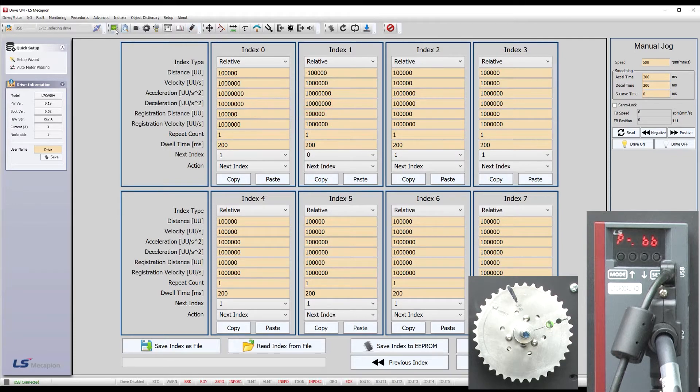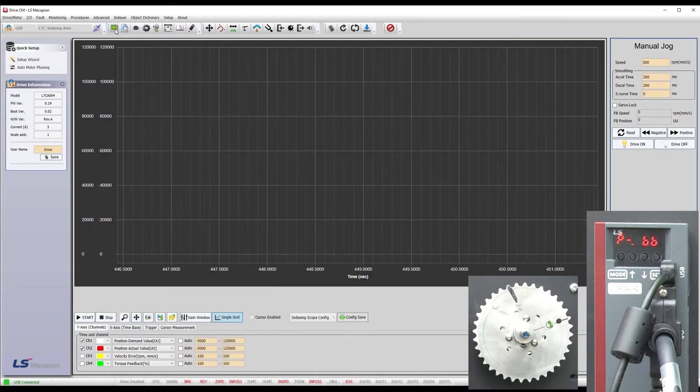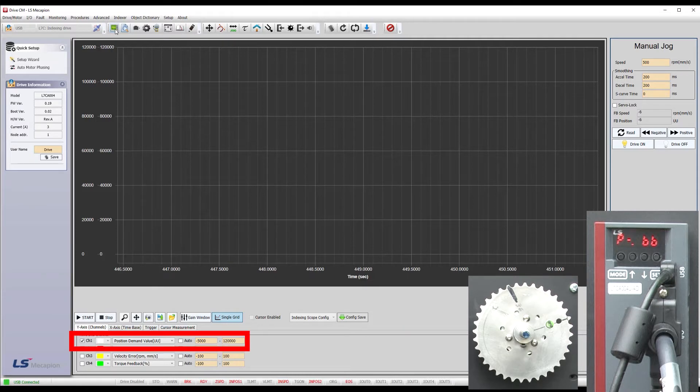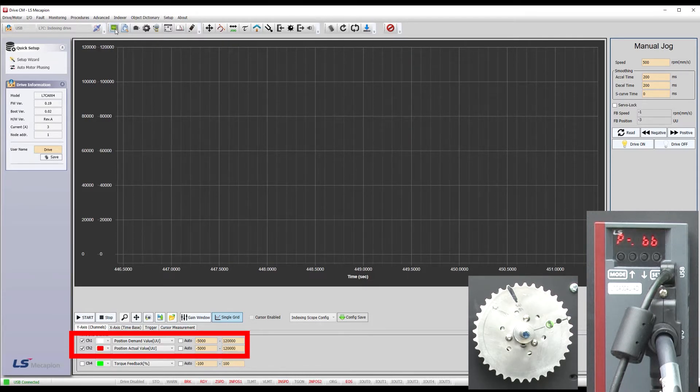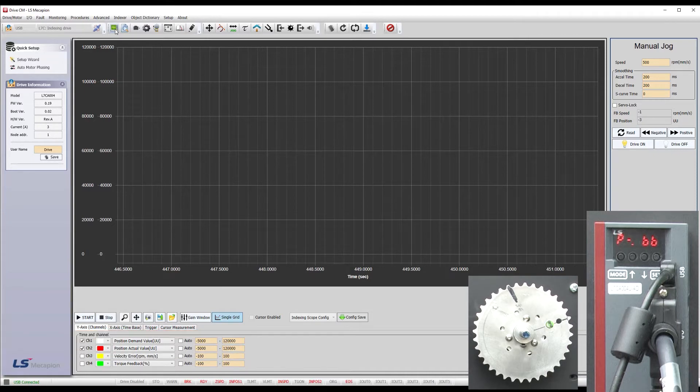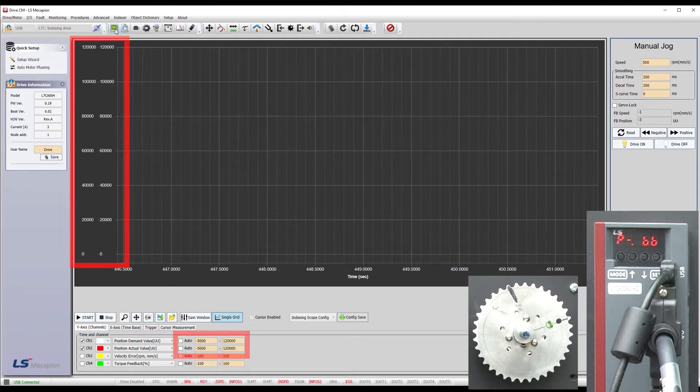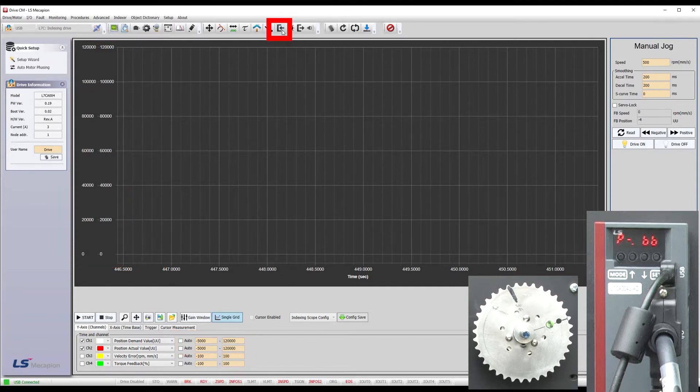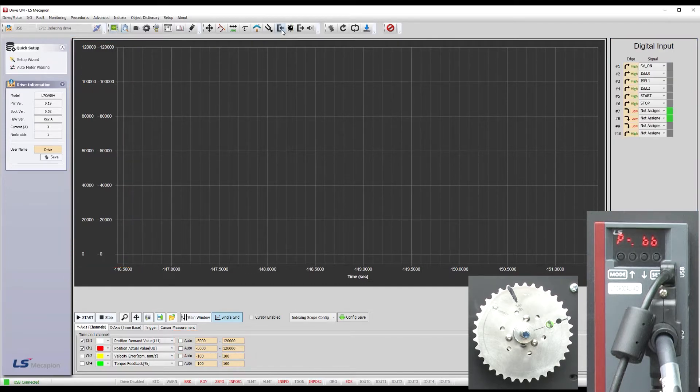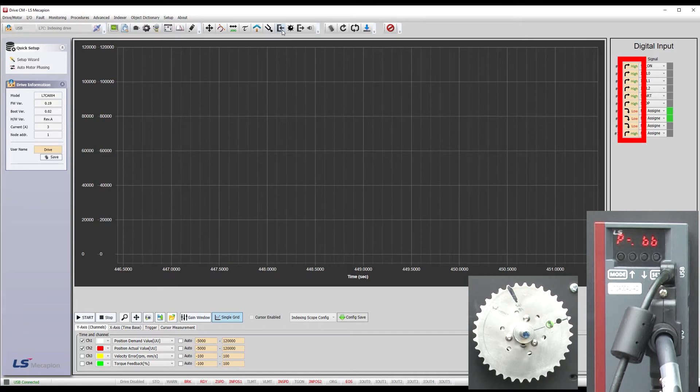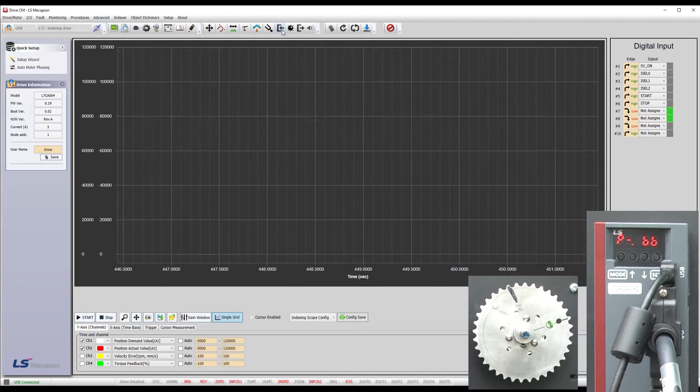Let's bring up the scope which I have already set up with the commanded position, this software calls it the position demand, and the actual position. I also set the vertical scale to show us the 0 to 100,000 user units of motion we set up. If it isn't already up, click this guy to bring up the digital inputs. We'll click on these guys to override any wires or actual switches that may be connected to the drive. I love that I can override any wiring that might be installed.